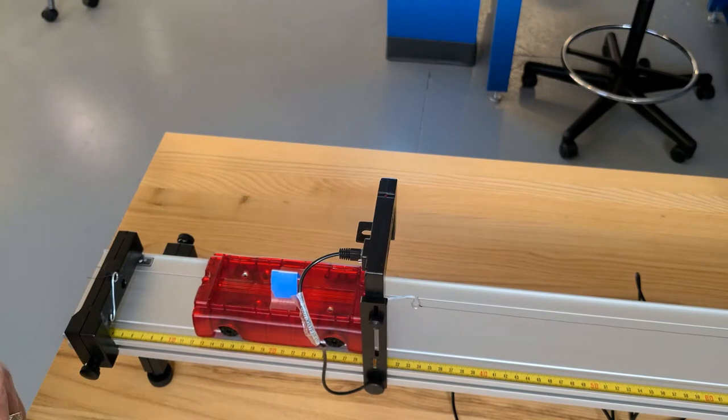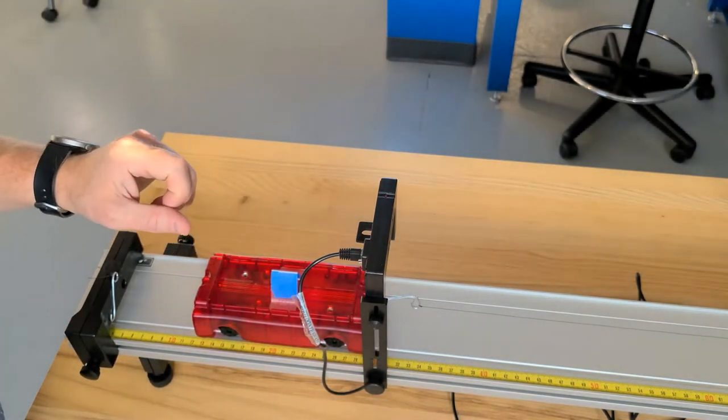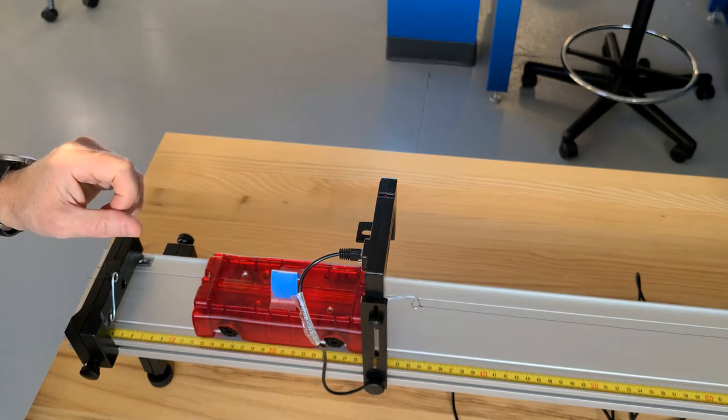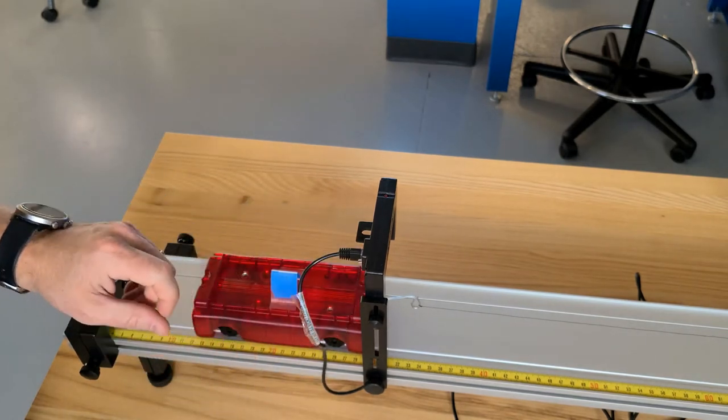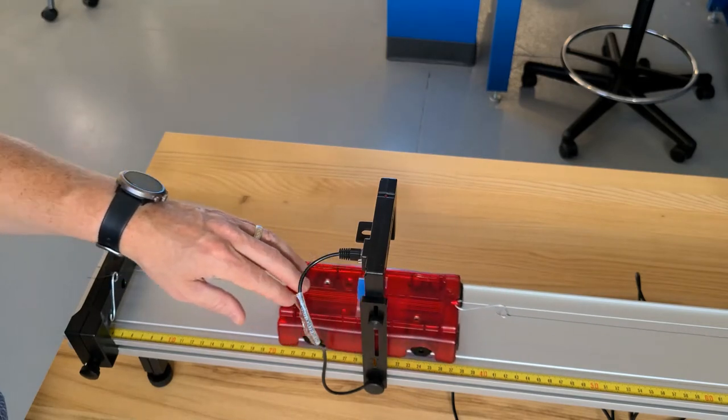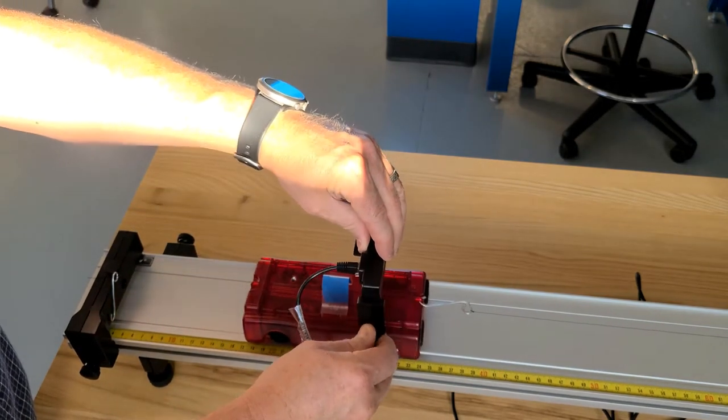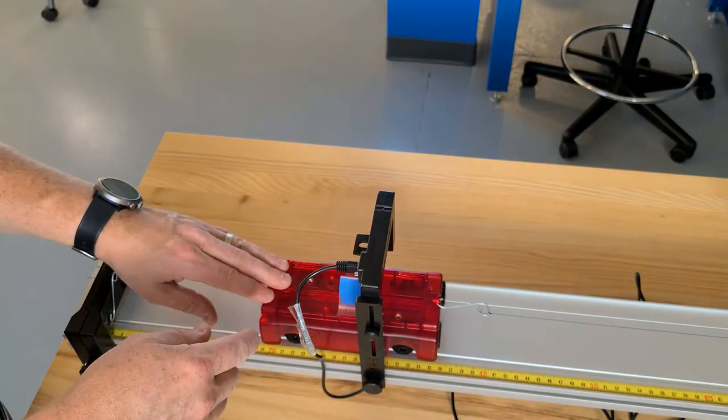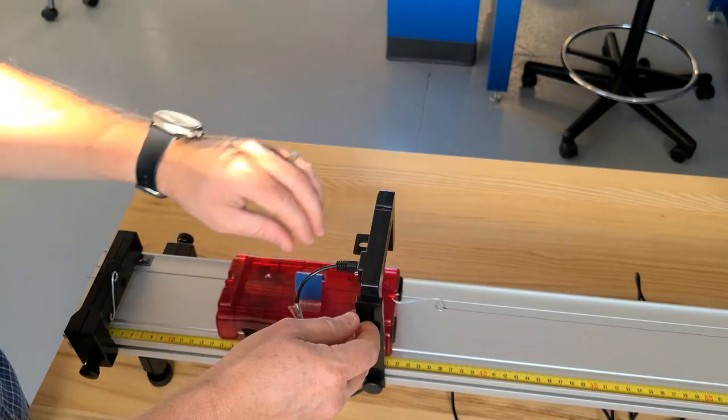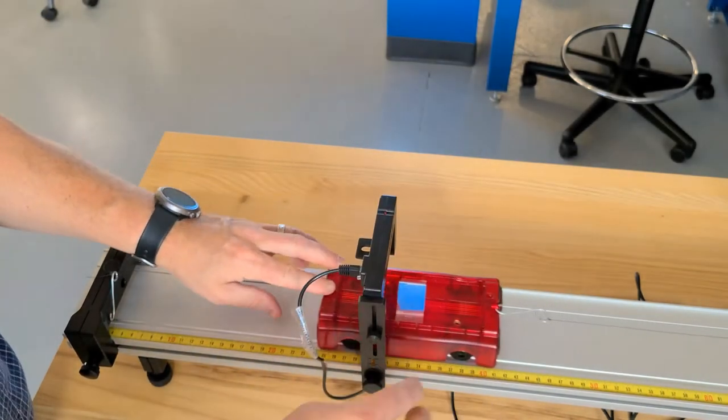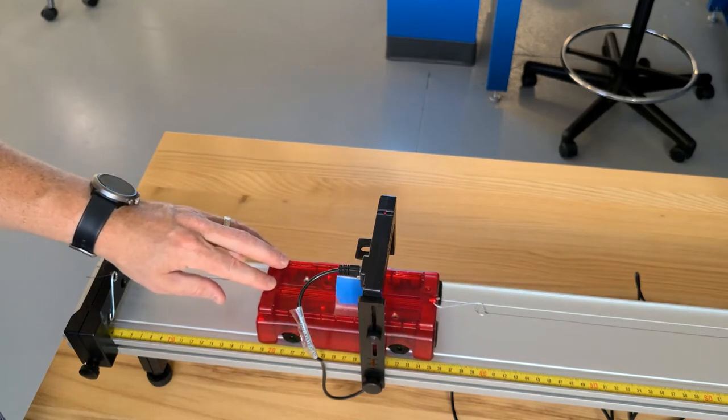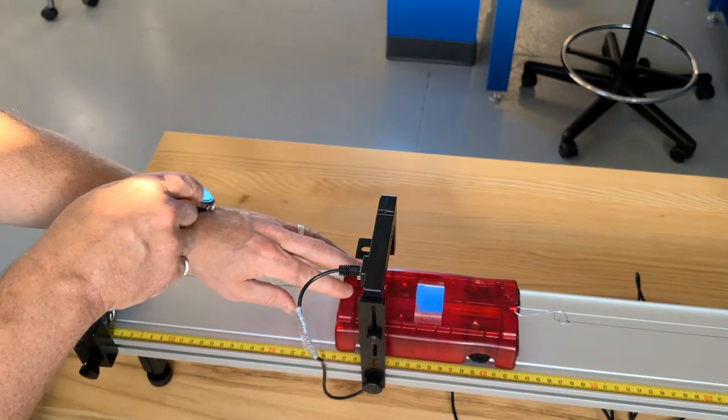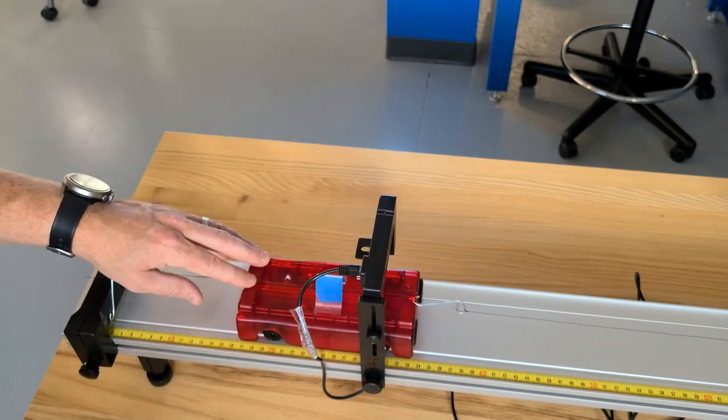The photo gates are equipped with an IR sensor and a little indicator light on top so that you can tell whether or not it's actually read the part going by. You may need to adjust the height in order for the sensor to detect. If I pass through, you see the light's not activating, so I need to adjust my height of my photo gate down a little bit. Make sure it doesn't come in contact with the cart. As you can see now, I can go underneath it, it activates the light as it passes through, and the light goes off as it's gone and I'm not making contact anywhere.